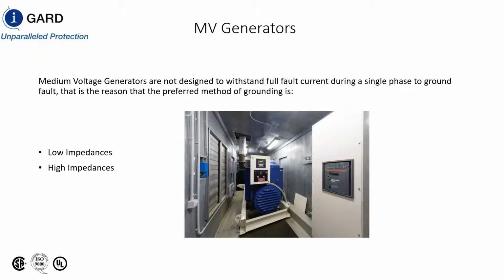So medium voltage bus connected generators aren't designed to carry a great deal of single phase to ground fault current. In fact, you can probably generate more single phase to ground fault current if you have a single phase fault in a generator than the 3-phase bolted fault current, because there's such a low impedance. So you must have a low or high impedance grounded system. Typically, this is a low or high resistance grounded system. However, you can use reactors in this particular case as well. But what you want to do is you want to protect the generator specifically for single phase to ground faults.